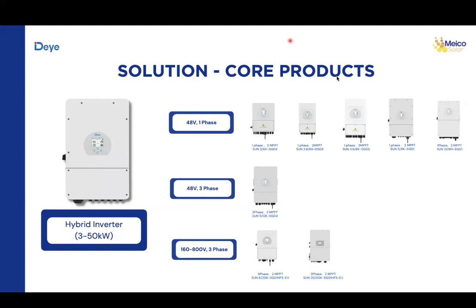So that's a really good question, Steve. Fortunately, with Deye, you can fit the three-phase solution for low voltage applications, so that it's 127 to 220, regardless of the frequency. So you can have it at 50 hertz or 60 hertz. It's completely set up free whenever you are commissioning the product. So you can have a 60 or 50 hertz solution, low voltage applications. That's really good because we know across the Caribbean there are a bunch of different grids and grid needs. So you can fit it basically to whatever grid you will find, 60 or 50 hertz, three-phase low voltage. In this case, it's completely good to go, okay?